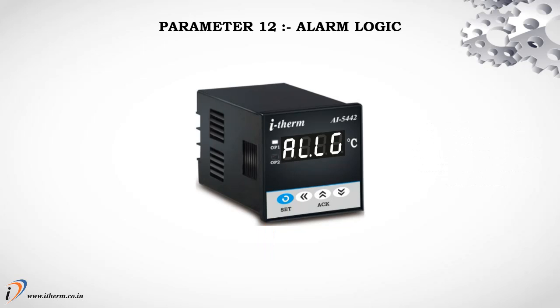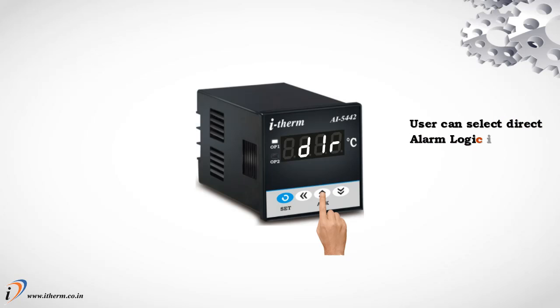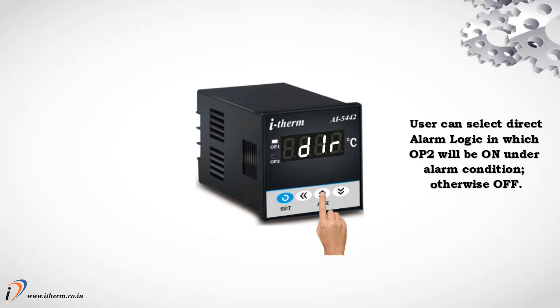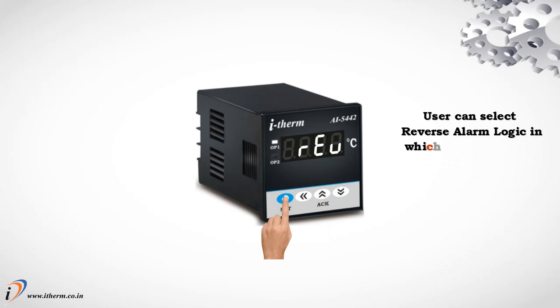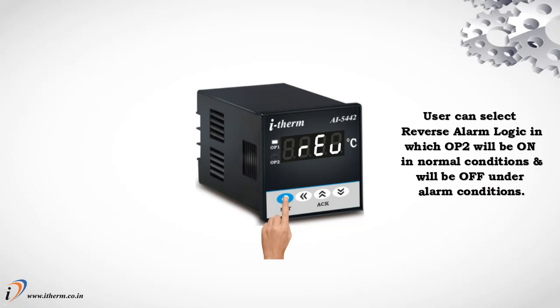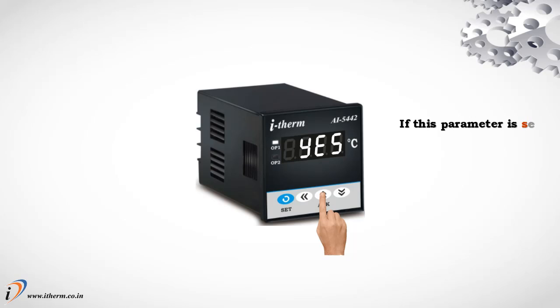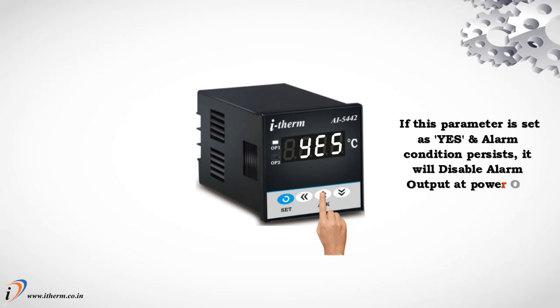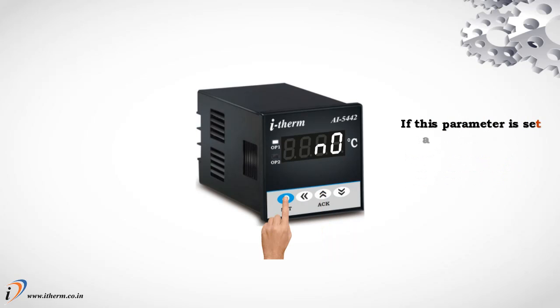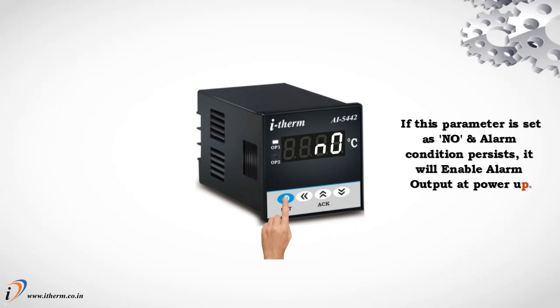Parameter 12. Alarm logic. User can select direct alarm logic in which output 2 will be on under alarm condition, otherwise off. User can select reverse alarm logic, in which output 2 will be on in normal conditions and will be off under alarm conditions. Parameter 13. Alarm inhibit. If this parameter is set as yes and alarm condition persists, it will disable alarm output at power on. If this parameter is set as no and alarm condition persists, it will enable alarm output at power up.